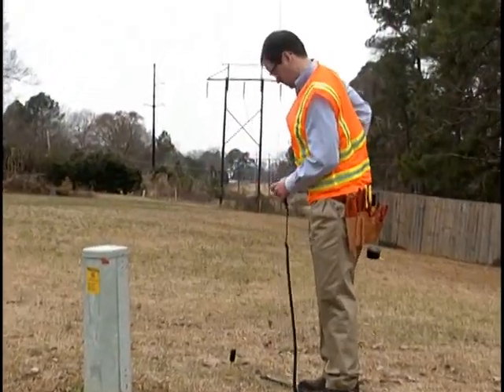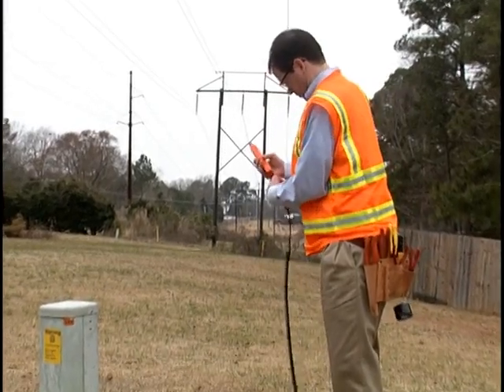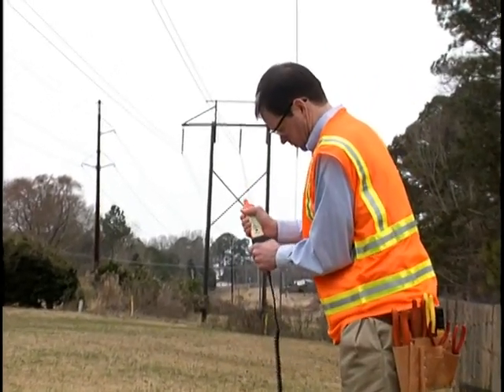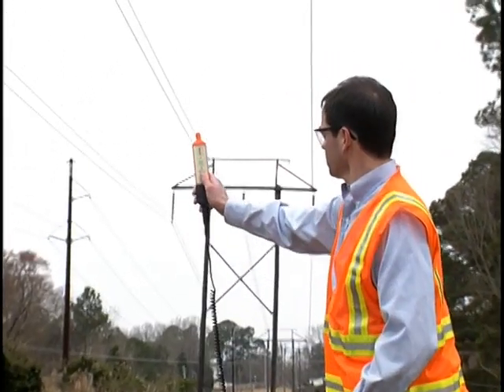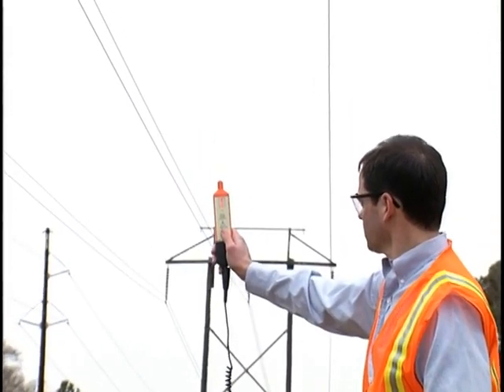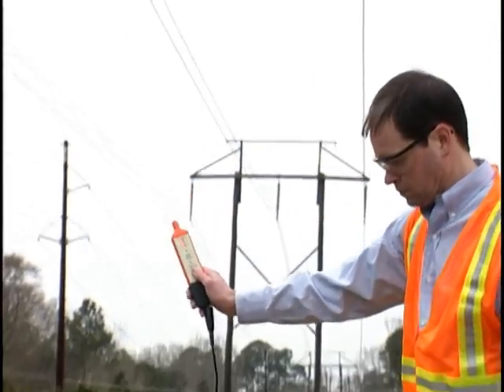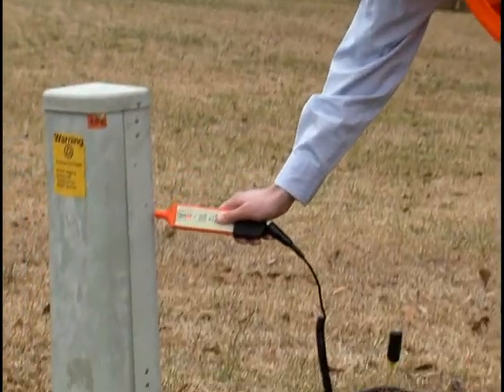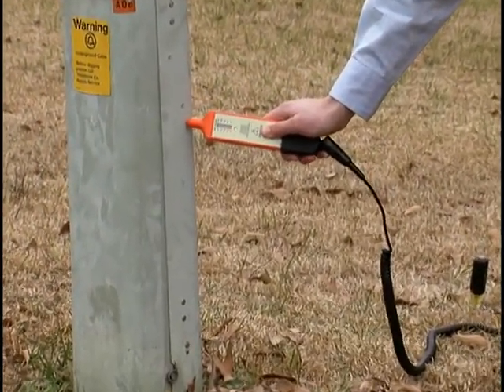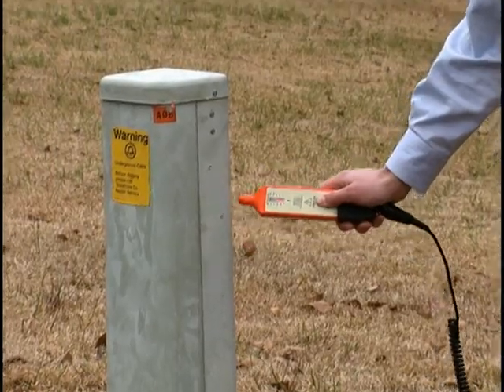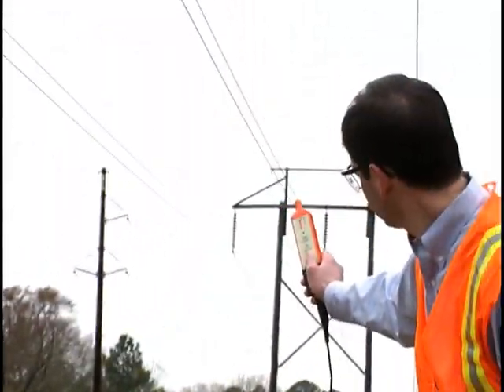The presence of this electric field is demonstrated by standing under 230 kV power transmission lines with the FVD indicating hazardous voltage. As you move the FVD closer to a grounded object, such as this pedestal, the voltage from the E field collapses. As we move the FVD away from the pedestal, the voltage increases.